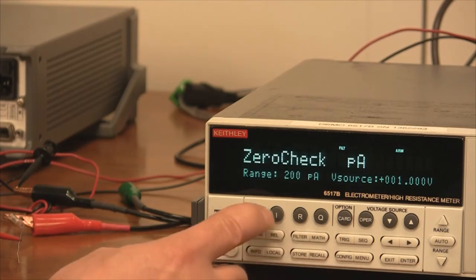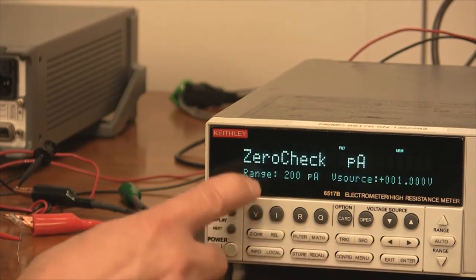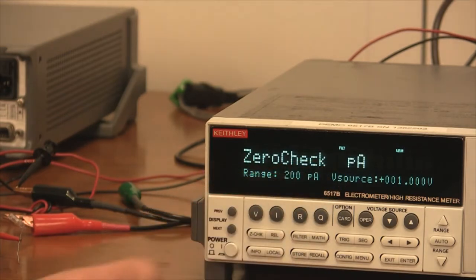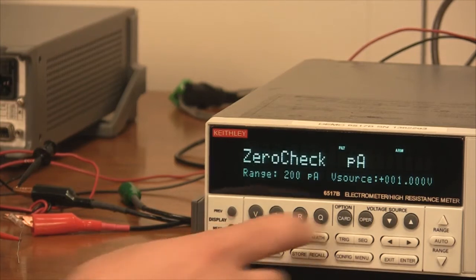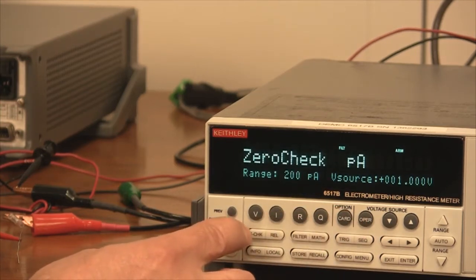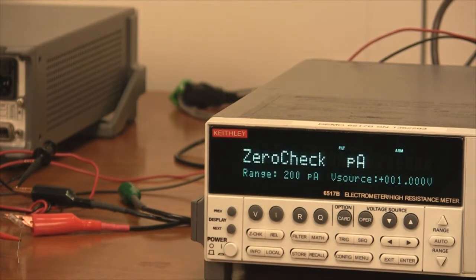You select the current function. We're going to select the 200 picoamp range. Now we can also show resistance, but we'll get to that in a second. And then we would hit operate and release zero check. Okay, we're going to do that in a second.